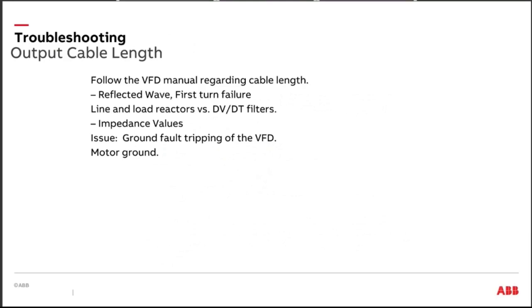There's a couple things that we can do there. We can use a dV/dt filter. Sometimes you might even have somebody that recommends a sine wave filter. Sine wave filter is fine, but just remember, sine wave filters are expensive. They're not cheap, and they're not little bitty guys. They're a good sized piece of equipment, and they're almost like having another drive there. So now you have your drive sitting there producing heat, and your sine wave filter producing heat, and you've got to take into account all that heat that's generated.